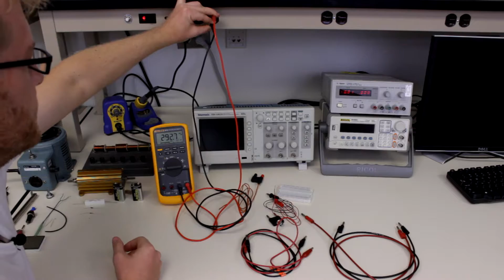Since the neutral and ground are connected at the breaker box, I shouldn't measure any potential difference between them, but I do measure around 300 millivolts RMS, and I leave it to you to figure out why. Remember, this forms a loop with the terminals at the junction box, and this is AC voltage, so that may give you a clue.